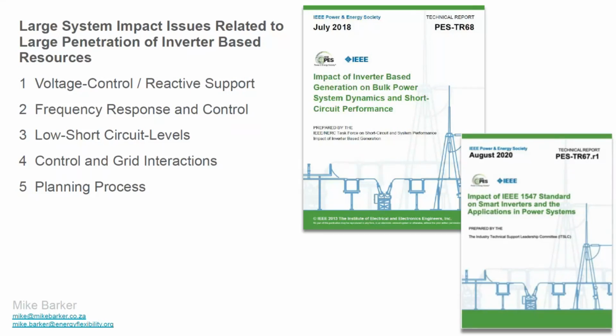The word smart inverters, to many of us, implies that the inverter complies with 1547—marketing guys call anything smart these days—but really it should mean an inverter with intelligence that can play nicely with the grid. Looking at the requirements and impact: voltage control and reactive support are needed, along with frequency response and control, and then short circuit levels need to be taken care of.